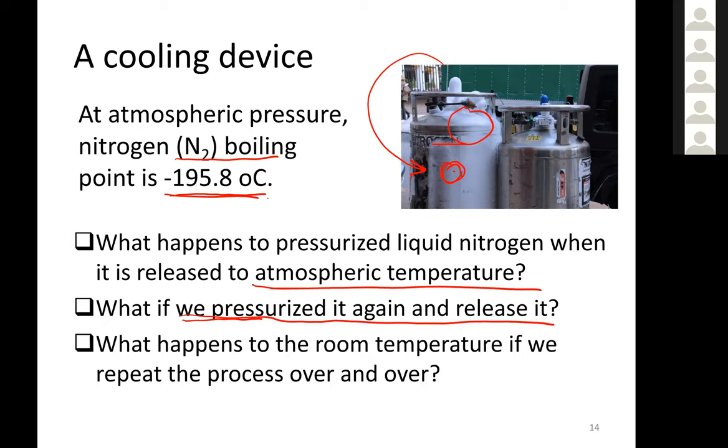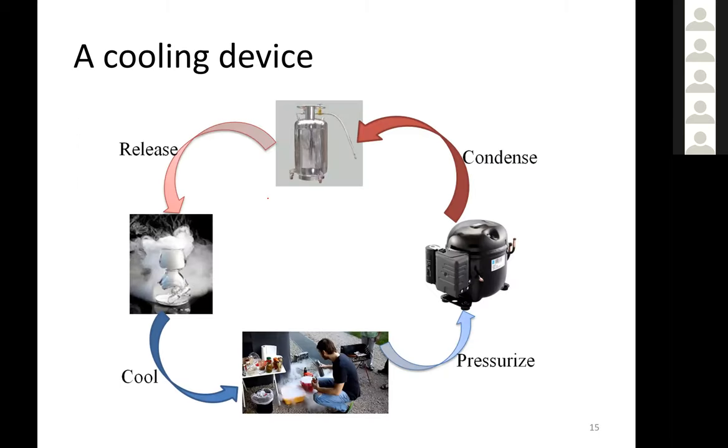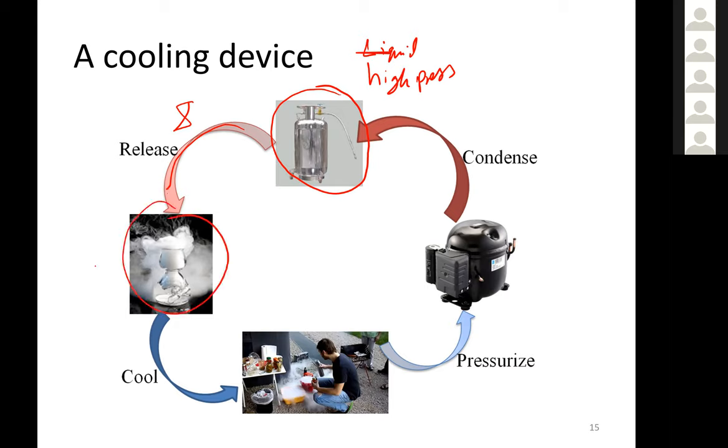And that's exactly what happens in the air conditioning process. Initially we have high pressure refrigerant, that's liquid, at high pressure. I have an expansion valve, and that expansion process is going to drop the pressure down to the phase change point or the boiling point at the evaporator pressure. So here I have one pressure value, high pressure value, and here I have low pressure value.